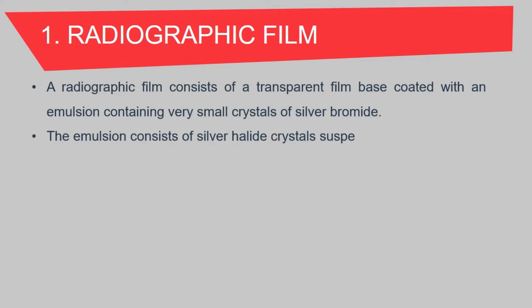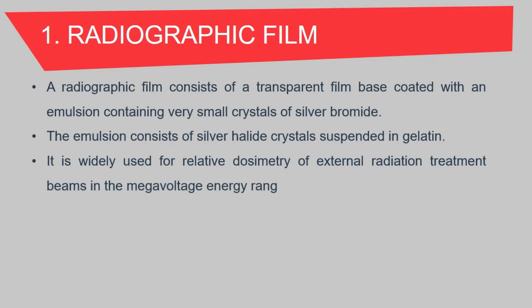The emulsion consists of silver halide crystals suspended in gelatin. It contains 95% silver bromide and 5% silver iodide. It is widely used for relative dosimetry of external radiation treatment beams in the mega voltage energy range. This film is used because of its high spatial resolution, low cost and wide accessibility. This image shows a film badge dosimeter that is widely used as a personal dosimeter.